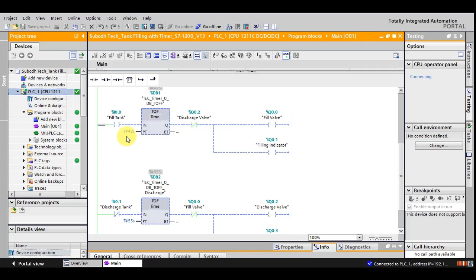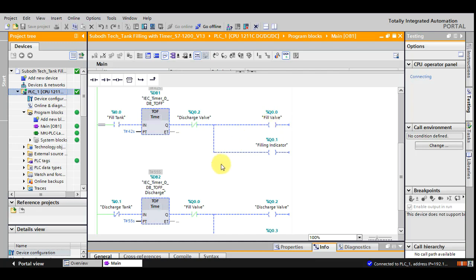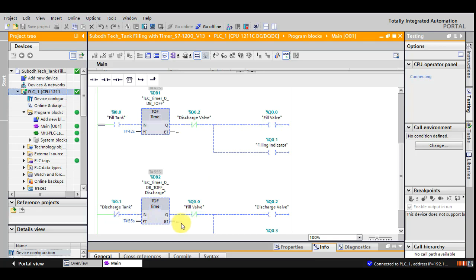So what happens is, when the fill push button is pressed, these two outputs have got on. So I have taken normally closed contact of the fill valve Q0.0 output, and I have kept it here at the discharge rung. So when this output would get on, even if someone is pressing the discharge push button, this input is getting energized. Then also, when it is on, it will not allow to get the discharge valve on.